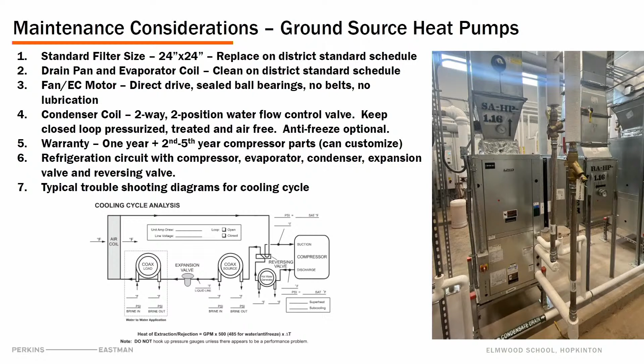The warranty we talked about, we can't customize it. That's what that should say. We cannot customize it. The refrigeration circuit, again, we talked about: just a basic compressor, evaporator, condenser, expansion valve and reversing valve. So I say a refrigerator with ductwork on it. It almost looks like a refrigerator. And then there's some pretty easy troubleshooting. If Tim got into a scenario where he had to do something, he's got a refrigeration technician. You can hook gauges up to it and easily tell what's going on with the system. So it's pretty simple from that perspective. Any questions about this slide? Any other commentary from Tim or Chris?